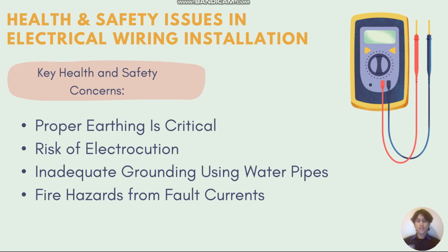For example, without proper grounding, fault current cannot safely flow to earth, increasing the chance of overheating wiring and causing electrical fires. Okay, for the detailed example one, an ungrounded ceiling fan metal clad could be energized during a fault, causing electric shock risk to restaurant staff. And for example two, using the water pipes as earth may fail if the pipe is damaged or insulated, failing to trip the circuit breaker during a fault, thus increasing the risk of fire and injury.